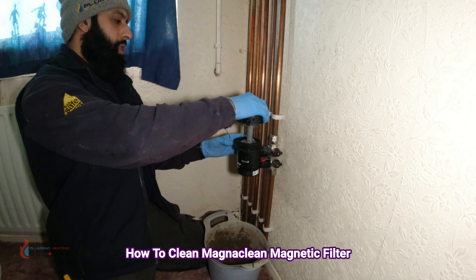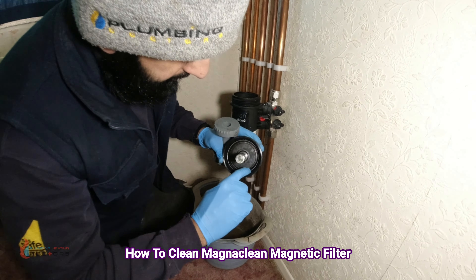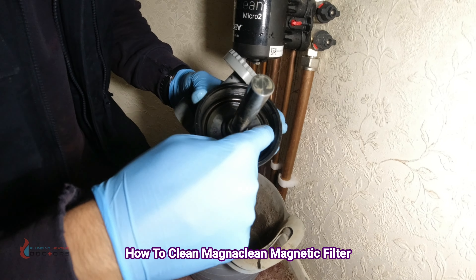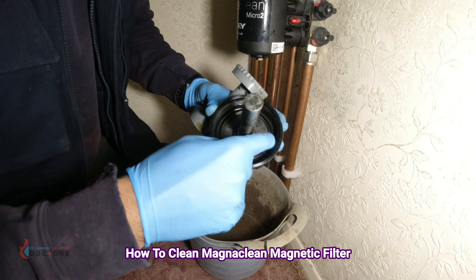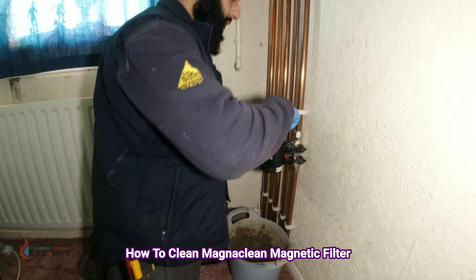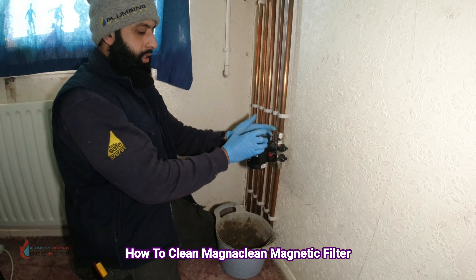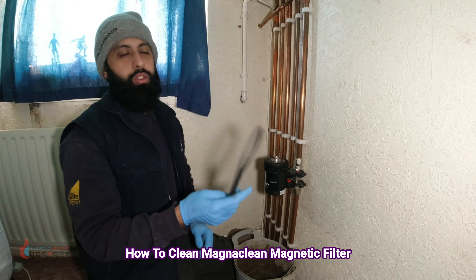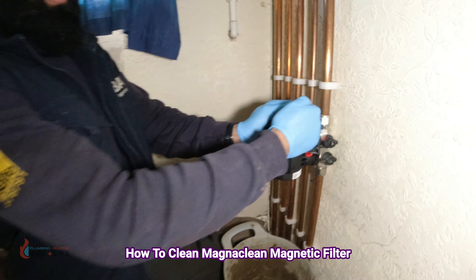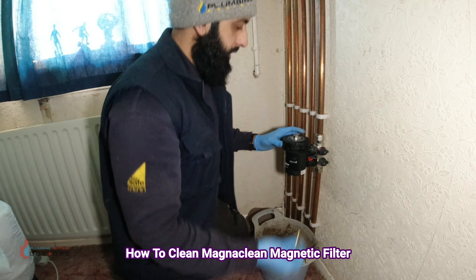We put the inhibitor in and we're ready to put the lid back on. Before doing so, check the rubber seal inside the lid — make sure it's in good condition. If it isn't, that's usually why the lid leaks. You can get replacement rubber washers from Adey for free if it leaks. To close it, I only use the tool to open — not to close, as you'll over-tighten it. Just get it hand tight and you're done.